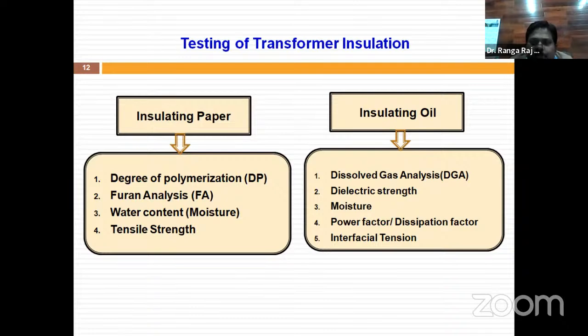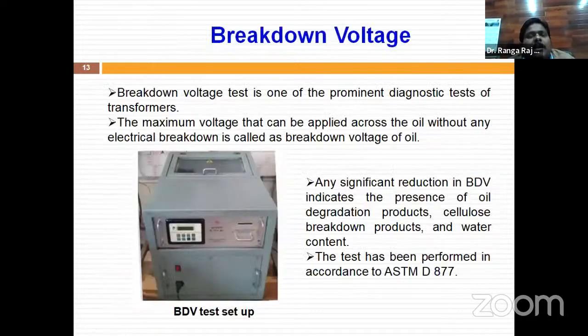Next, power factor, interfacial tension. So if you perform at least 2 to 3 tests out of these 10 tests, or 3 to 4 tests, we can confidently determine the health of the oil and the transformer.